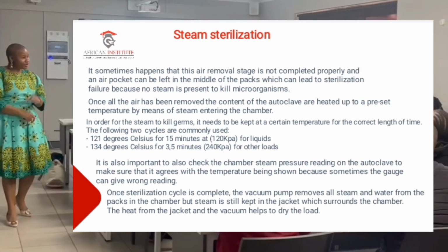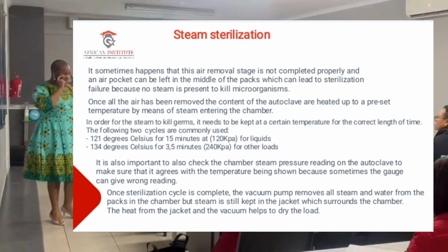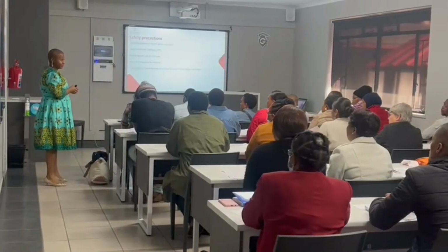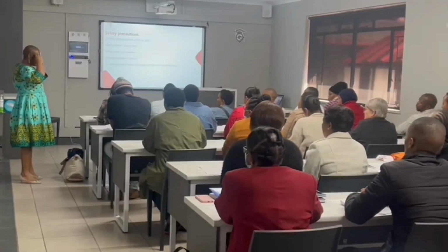It is also important to check the chamber steam reading on the autoclave to make sure that it agrees with the temperature being shown, because sometimes the gauges can give wrong readings. Once the sterilization cycle is complete, the vacuum pump removes all steam and water from the packs in the chamber, but steam is still kept in the jacket which surrounds the chamber. The heat from the jacket and the vacuum helps to dry the load.